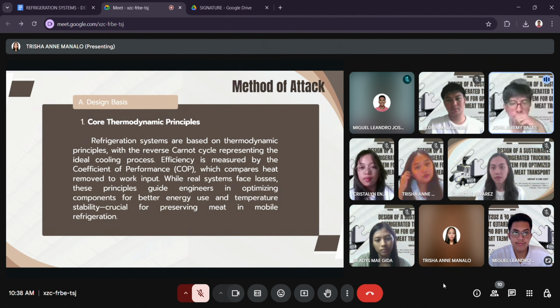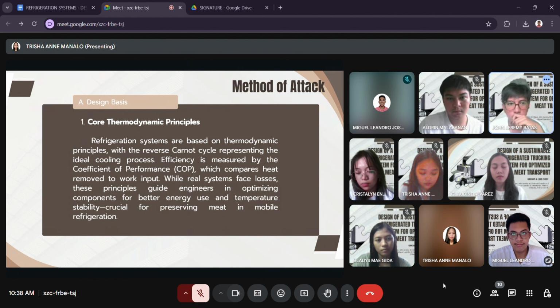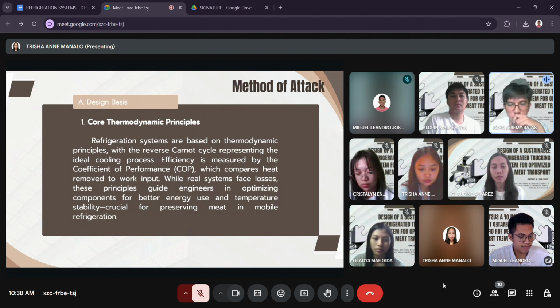To develop an effective refrigeration system for meat transport, we started by identifying the core thermodynamic principles. The system follows the reverse Carnot cycle, which serves as the ideal model for the cooling process. While real systems are never perfectly efficient, this principle helps guide design decisions. We measure system performance using the coefficient of performance, or COP, which compares the amount of heat removed to the work input. Our goal was to improve both energy efficiency and temperature stability, critical factors for preserving meat during transport.